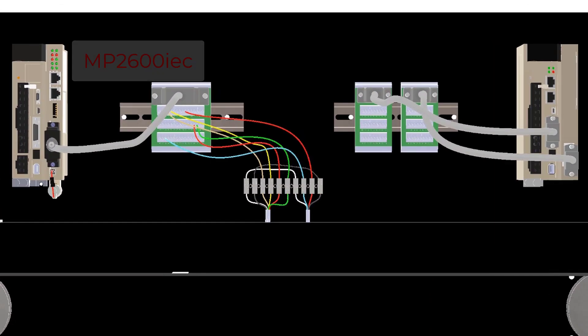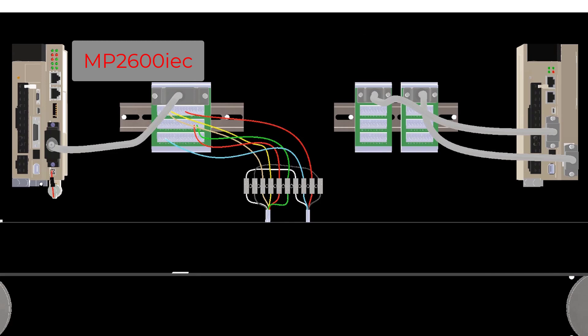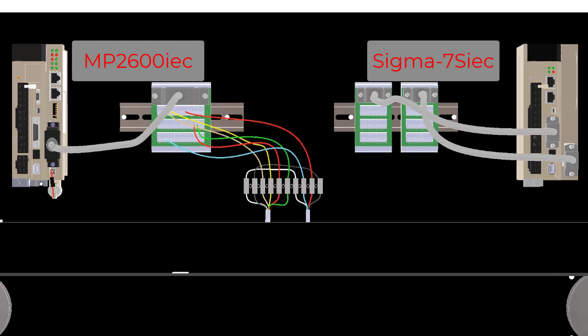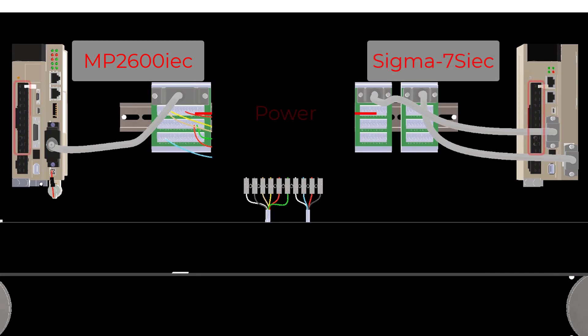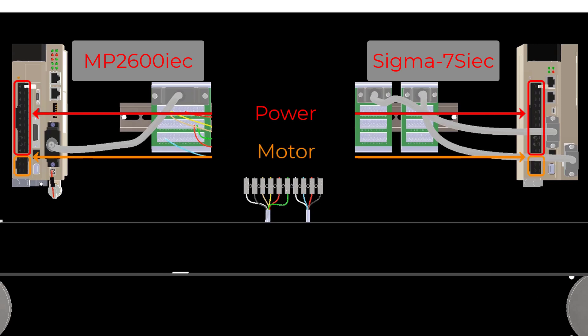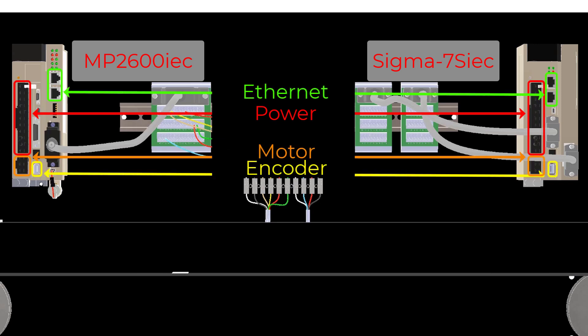Let's start with Step 1 by looking at the wiring changes that need to be done. Currently all of the wiring is coming into the MP2600 IEC. The Sigma-7S IEC has the same voltage requirements so the power, motor, encoder, ethernet, and safety connectors can be directly moved over.